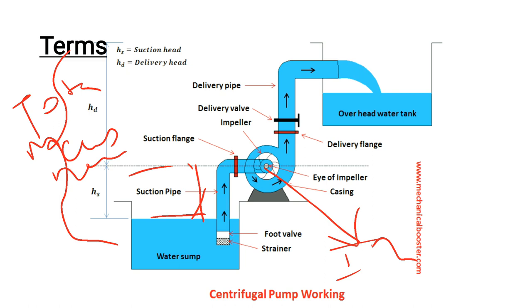The dynamic head includes the static head plus the friction head, discharge head, and hydraulic losses. Hydraulic loss includes losses due to friction, elbows, reducer valves, and other fittings in the pipe. Adding the velocity head gives us the total dynamic head.